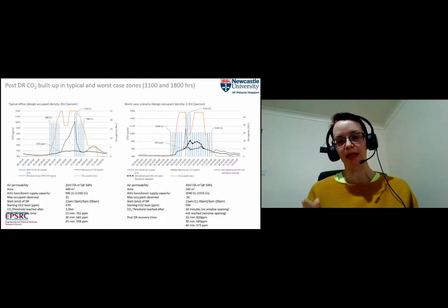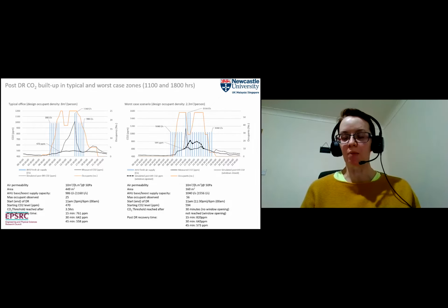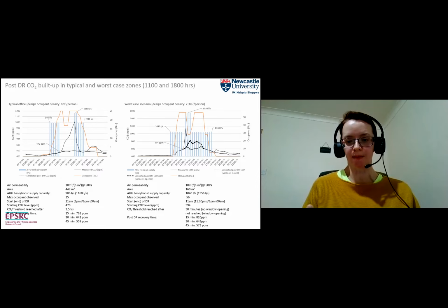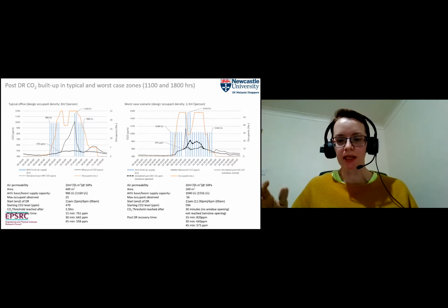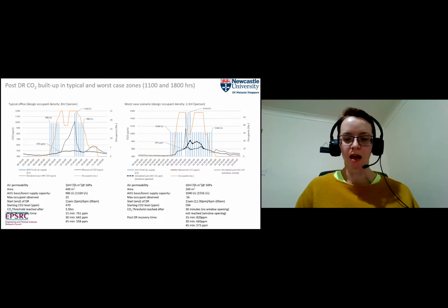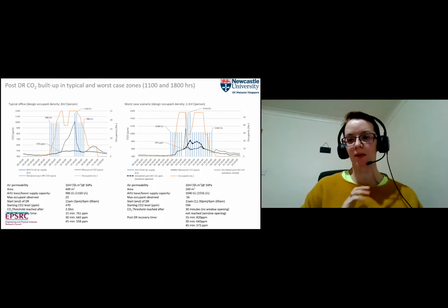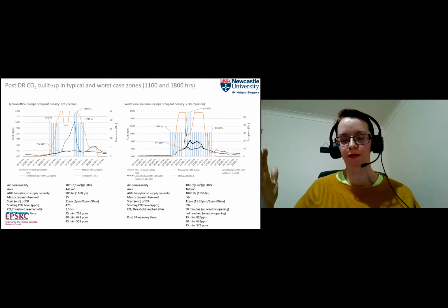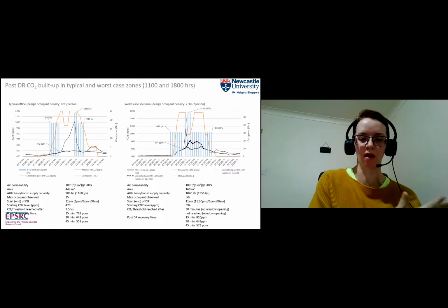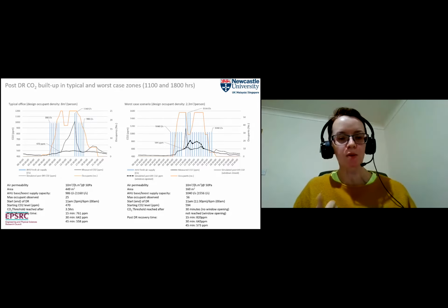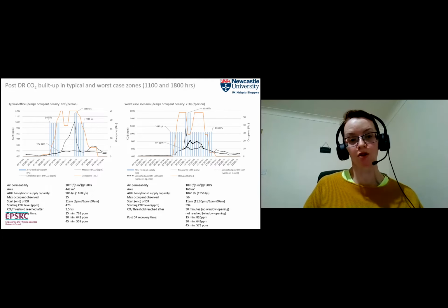When we've got a worst case space, so it's a reasonably small space, we looked at a small office in this case, then the air handling units are on to start off with in the morning. You can see those blue bars. We've got nice air handling unit fresh air rates happening. We turn them off at 10:30. We see what happens to the carbon dioxide levels, and they rise quite rapidly. In the case of this particular office space, we're exceeding carbon dioxide levels after 30 minutes. So we can only turn off and save and help the network for 30 minutes in that space compared to the more typical office space. So air handling units was one thing we looked at as something we could control differently.